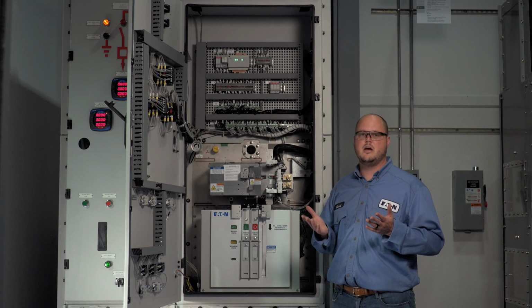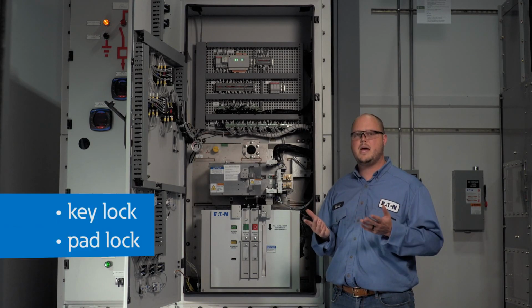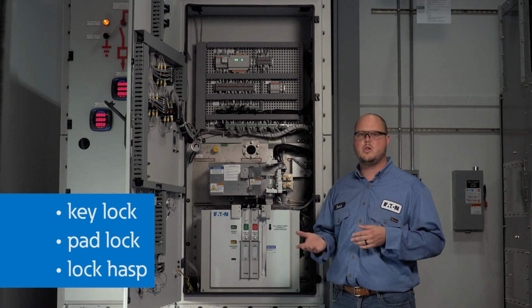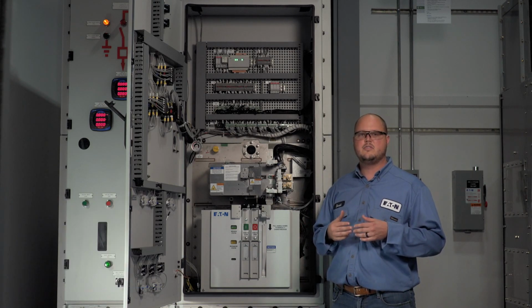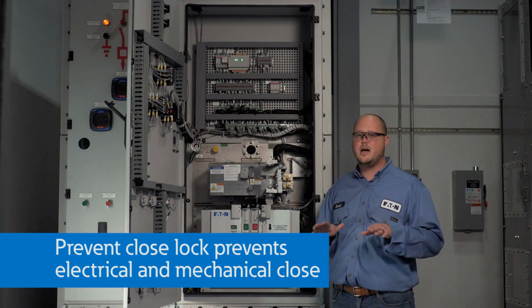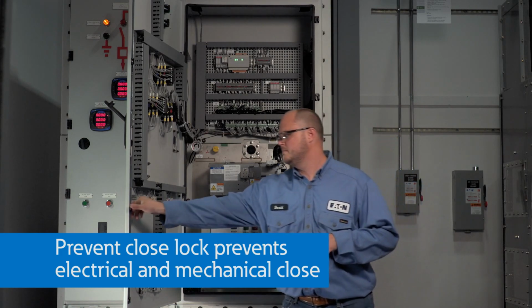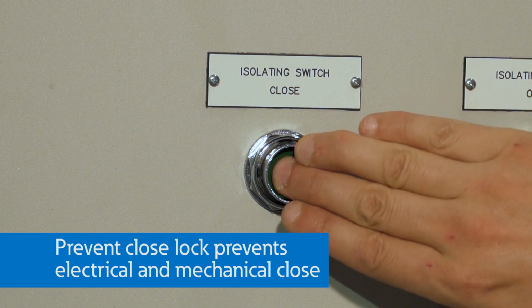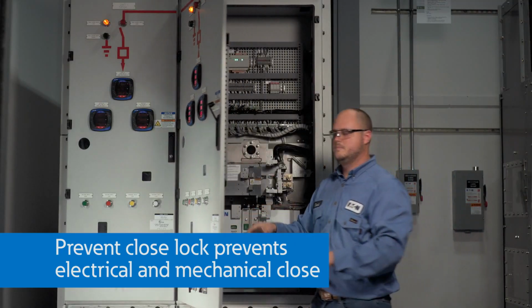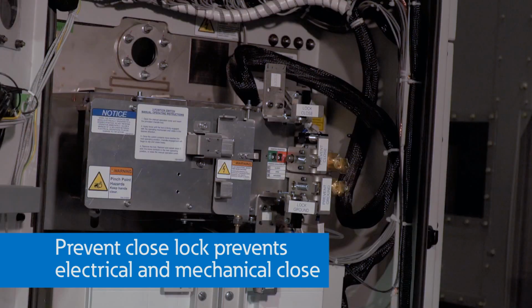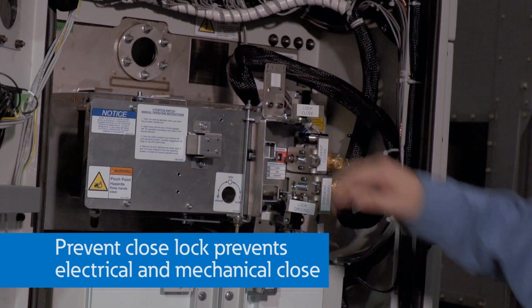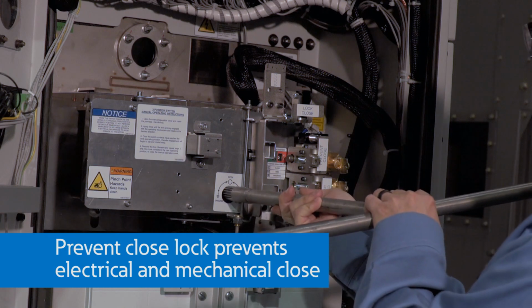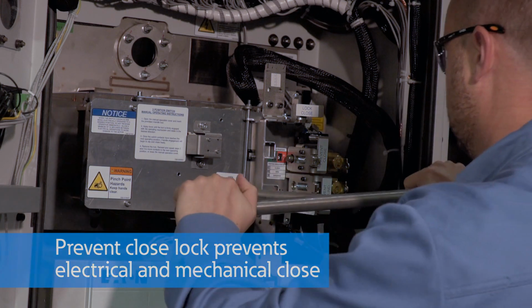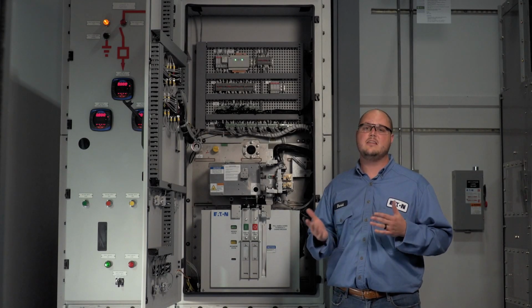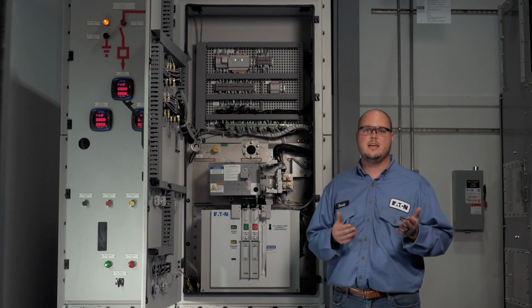All 4 of the switch interlocks can be locked with either a key lock, padlock, or a lock hasp, allowing multiple operators to apply their locks. After the prevent close lock is engaged, the switch cannot be closed neither electrically nor mechanically. However, you can see that the switch can in fact be moved to the ground position both mechanically and electrically.